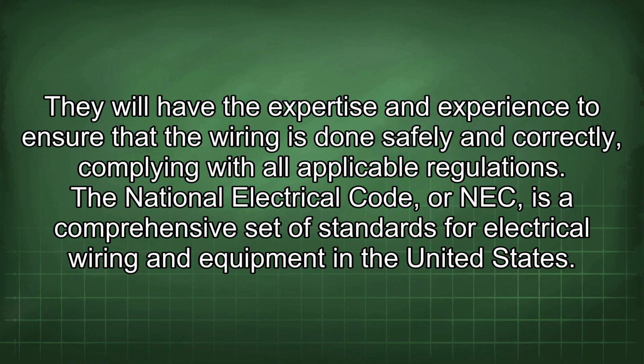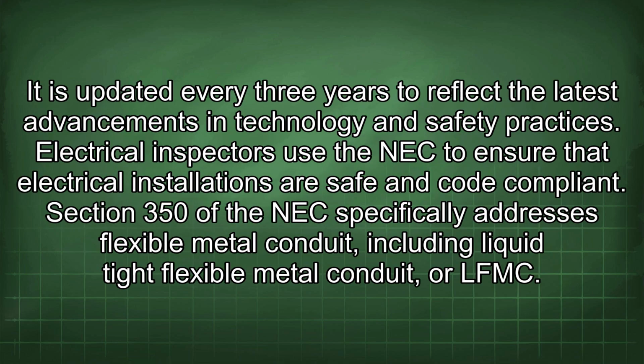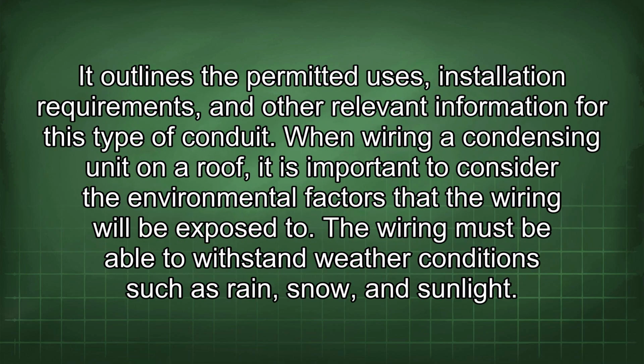The National Electrical Code, or NEC, is a comprehensive set of standards for electrical wiring and equipment in the United States. It is updated every 3 years to reflect the latest advancements in technology and safety practices. Electrical inspectors use the NEC to ensure that electrical installations are safe and code compliant. Section 350 of the NEC specifically addresses flexible metal conduit, including liquid-tight flexible metal conduit, or LFMC. It outlines the permitted uses, installation requirements, and other relevant information for this type of conduit.